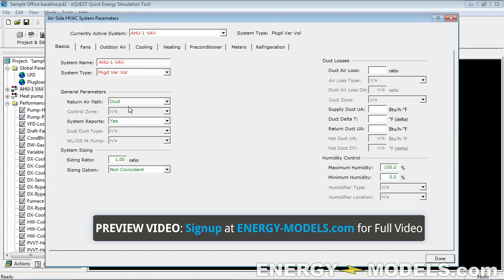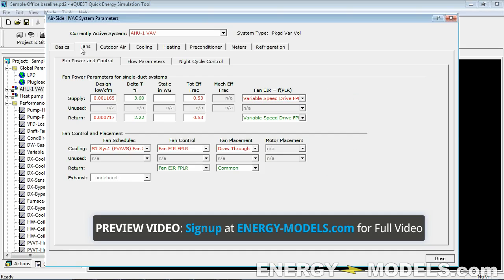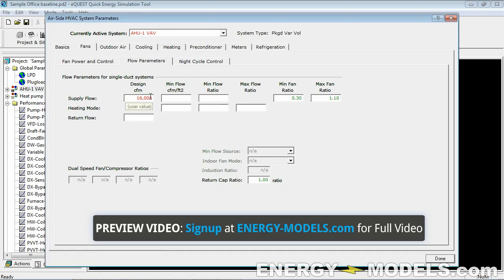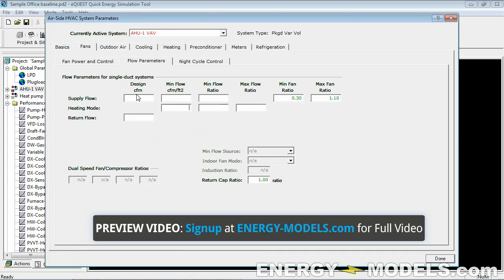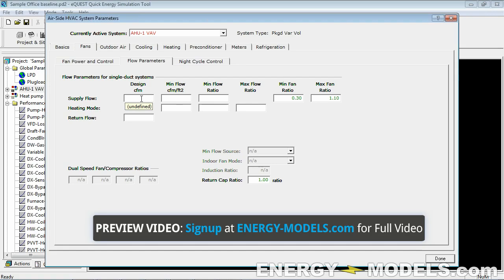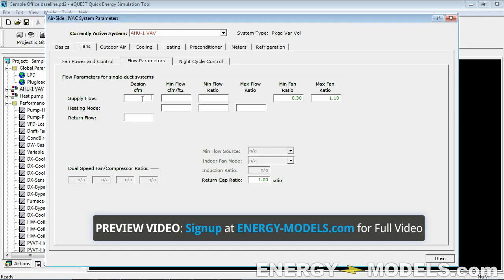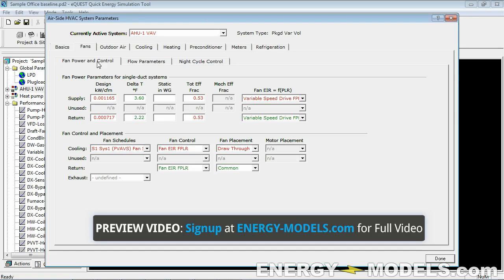We have to undo some of the stuff that we already did. For instance, the flow—just restore the default. eQuest is going to calculate the flow. We started with 16,000 CFM, but we just changed the envelope, changed all the glass type, and increased the lighting. So 16,000 CFM is probably not going to be enough anymore, and since we don't know that, we have to leave this blank.